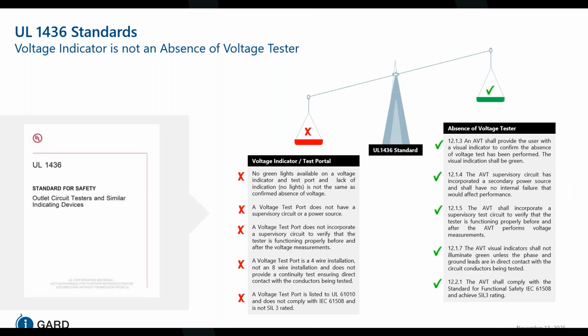Indicators only show the presence of voltage. If the lights are off, it does not guarantee that the circuit is de-energized. This can lead to dangerous false assumptions. Indicators also lack a supervisory circuit to verify proper operation, meaning they could fail silently due to installation errors or device faults. Additionally, they bring live voltage to the door, creating shock hazards during troubleshooting. On the other hand, an absence of voltage tester, i-AVT, is designed and certified to meet UL 1436 and IEC 61508 standards, including SIL3 safety integrity. AVTs perform an actual test at the point of work and include built-in checks to ensure the tester is functioning correctly before and after the measurements. They also illuminate when the test confirms the absence of voltage, eliminating the guesswork and reducing the risk. Simply put, AVTs provide a reliable, automated, and safer way to verify the equipment is truly de-energized, whereas voltage indicators cannot be trusted for this purpose.